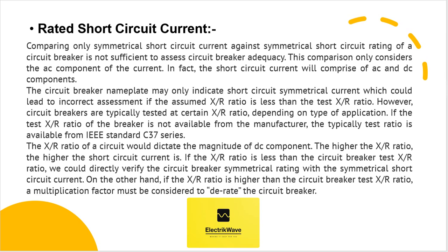However, circuit breakers are typically tested at a certain X by R ratio depending on the type of application. If the test X by R ratio of the breaker is not available from the manufacturer, the typical test ratio is available from the IEEE standard C37 series. The X by R ratio of a circuit dictates the magnitude of the DC component — the higher the X by R ratio, the higher the short circuit current. If the X by R ratio is less than the circuit breaker test X by R ratio, we could directly verify the circuit breaker symmetrical rating with the symmetrical short circuit current.